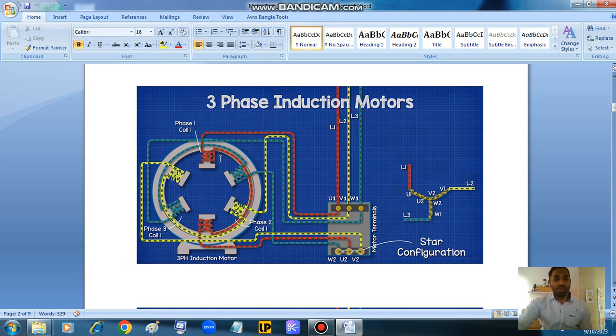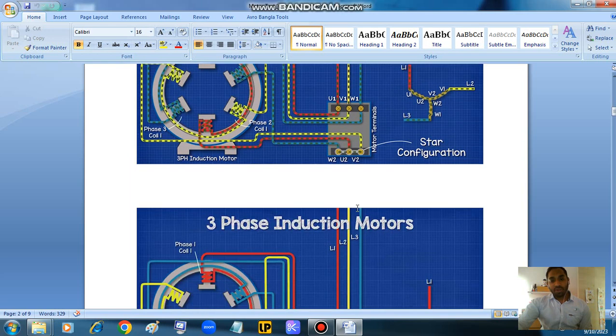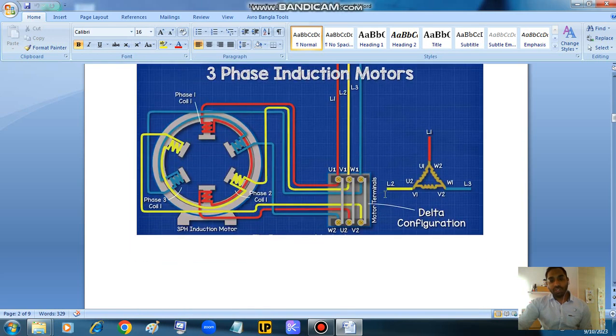This is the basics of an electrical motor, why the motor turns. And L1, L2, L3 are the power lines, the supply lines to the motor. This motor is connected in star configuration because U2, V2 and W2 are connected with a small plate. Next, we can see the motor terminals in delta configuration. Here, U1 W2, V1 U2 and W1 V2 are connected with three small plates.